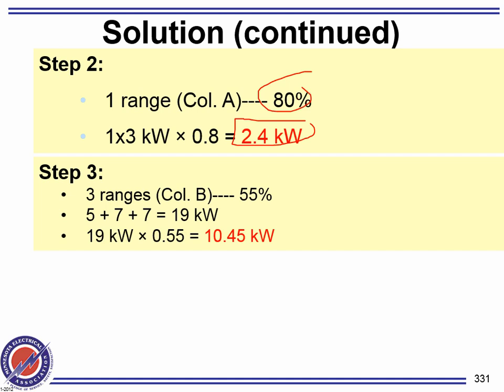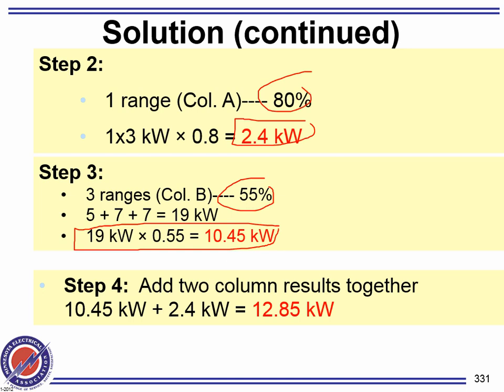Three of them. The rating for three is 55%. After you derate them, add them up and multiply by 55. That will give you this number. Then don't forget to add the two together, right? Add the two together. That will give you the total. And then compare them. Then compare them with what? So which number? Under C we got 17. Under A and B we got 4.85. Which one are you going to use? The lowest, 12.85. Any comments, guys, about ranges? Any comments, questions about ranges?